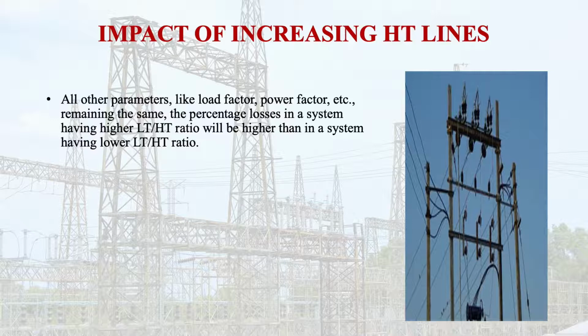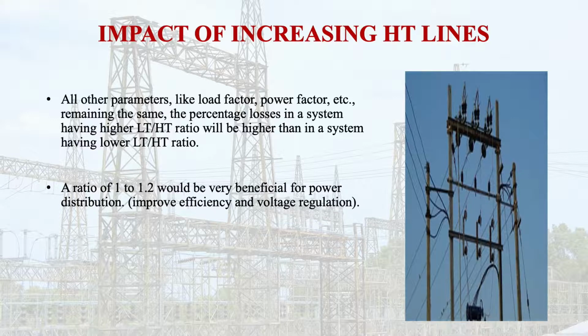All other parameters like load factor, power factor, etc. remaining the same, the percentage losses in a system having a higher LT to HT ratio will be higher than in a system having a lower LT to HT ratio. A ratio of 1 to 1.2 would be very beneficial for power distribution. As this measure is a must to improve the efficiency and voltage regulation of the distribution, additional capital investment should not come in the way.